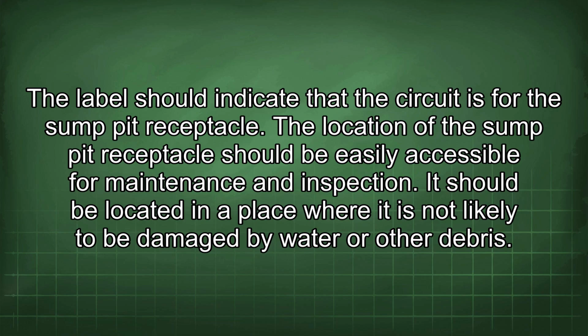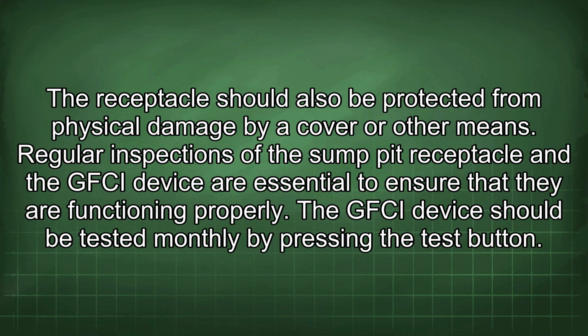It should be located in a place where it is not likely to be damaged by water or other debris. The receptacle should also be protected from physical damage by a cover or other means. Regular inspections of the sump pit receptacle and the GFCI device are essential to ensure that they are functioning properly. The GFCI device should be tested monthly by pressing the test button.